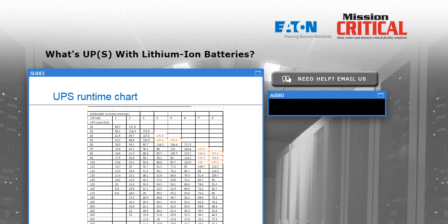Here's an example of a UPS runtime chart for a medium-sized UPS. I know this is a lot of numbers to look at, but across the top of the chart, in this medium-sized UPS under 200 kVA, you can go up to 8 battery cabinets and get reasonably large battery backup times, almost up to 3 hours.